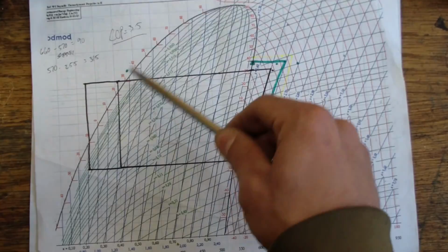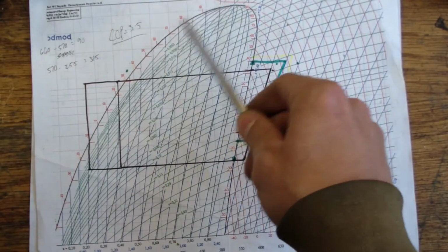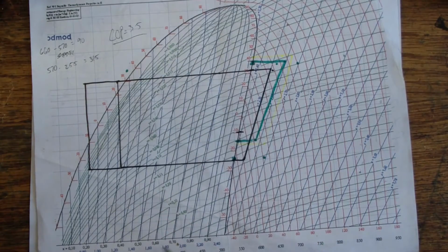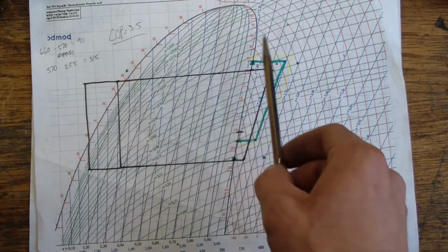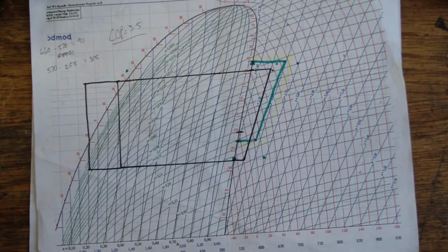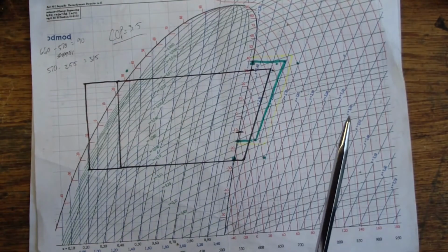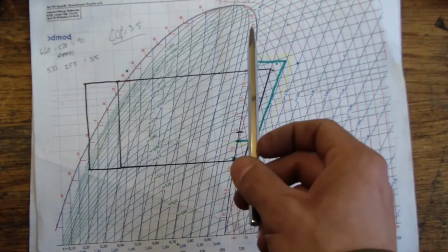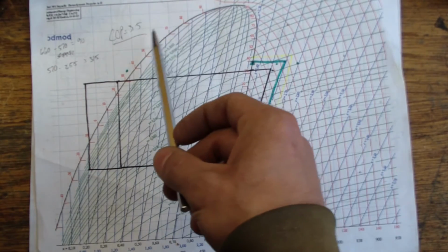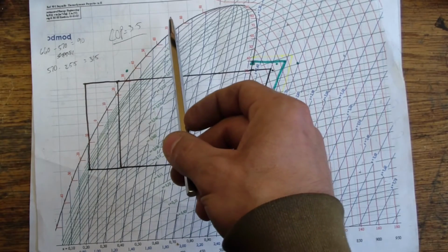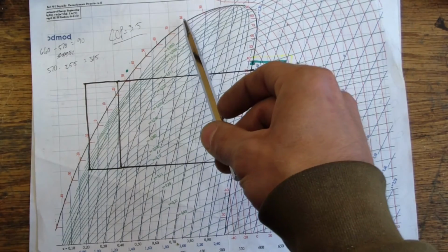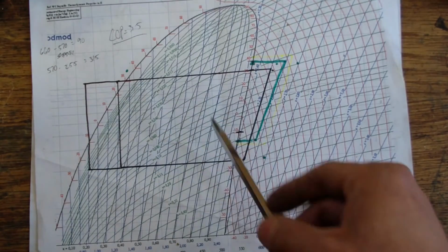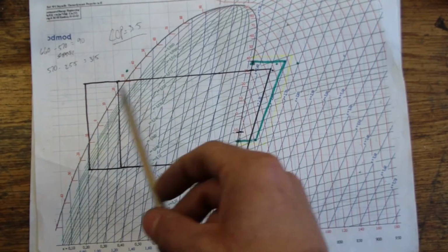And as we talked about before, the shape and the lean on this saturation curve changes, and it gets more pronounced towards the top. So if we were to operate this as a high temperature heat pump up here towards the top of the horn, we can see that the enthalpy change that occurs upon going from a vapor to a liquid or a liquid to a vapor is much smaller for every cycle of 1 kilogram or one pound of refrigerant. So not only do we have to circulate more refrigerant to effectively do our cooling or our heating work, but also we have to consider the amount of effective subcooling that we can do, because we're going to have to discharge more of that enthalpy, that heat, by lowering the temperature, doing actual sensible cooling of the liquid. Whereas down here we can operate more at a constant pressure and temperature and discharge that heat at a constant temperature and work in the latent heat part of things.